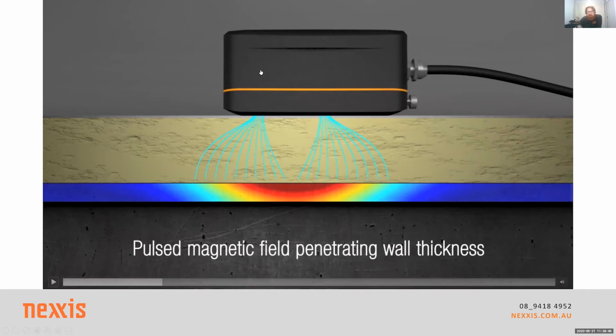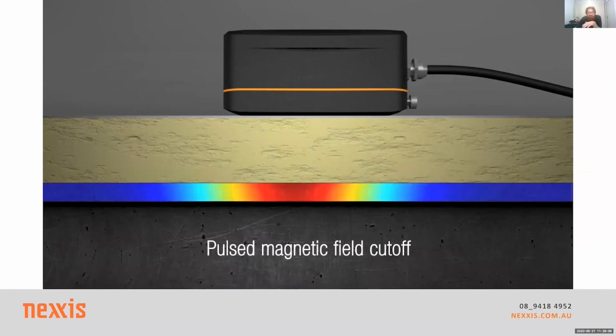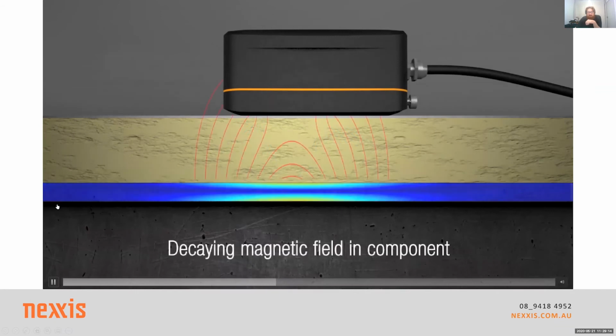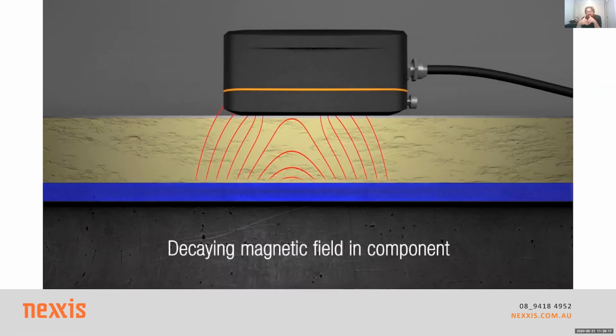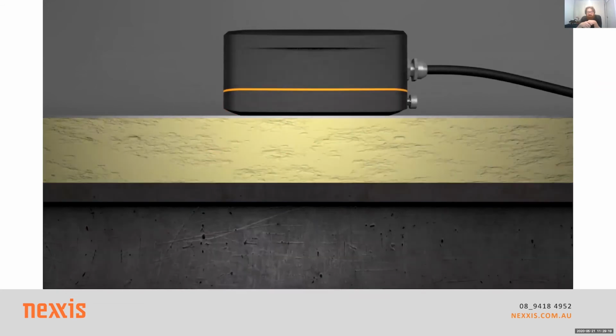We've got big coils in here - we run a current through them and get an electromagnetic field. That creates eddy currents, which create another perpendicular magnetic field. Then the easy part is done - next we turn off the probe. It shuts down quite quickly and hard, with electronics designed to shut down fast. Then we listen for the decaying magnetic field, which changes the impedance in the coils, and we can measure that.